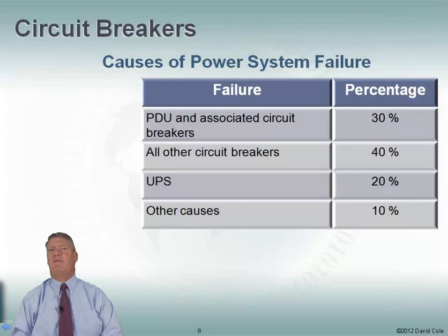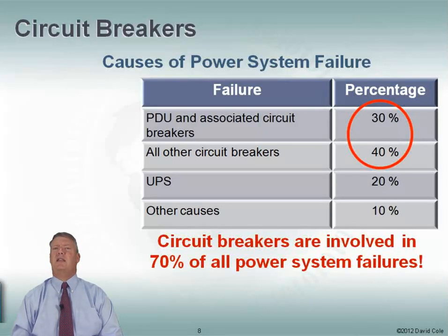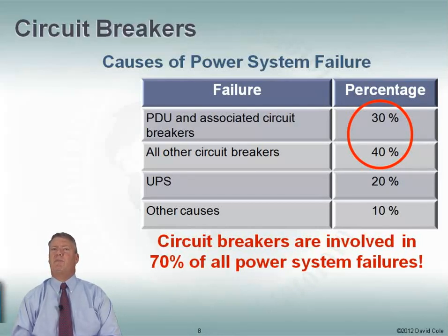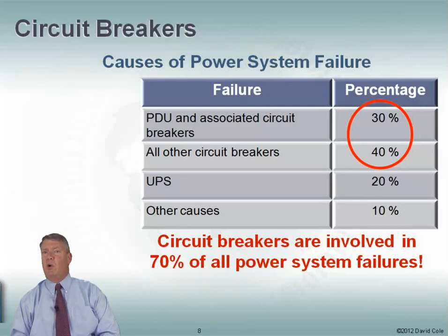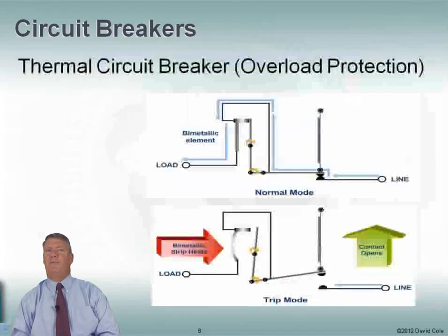Causes of power system failures: PDUs, circuit breakers, UPSs, and other causes. Look at these two together — 70% of all power system failures involve circuit breakers. So it's very important that we understand them. When circuit breakers are a problem, it's one of two things: either bad circuit breaker coordination, which we just talked about, or not understanding when the circuit breaker is supposed to trip. We'll talk about that in just a minute.